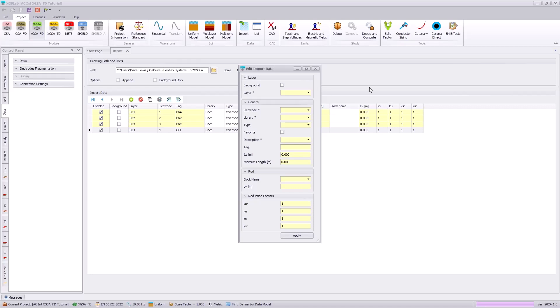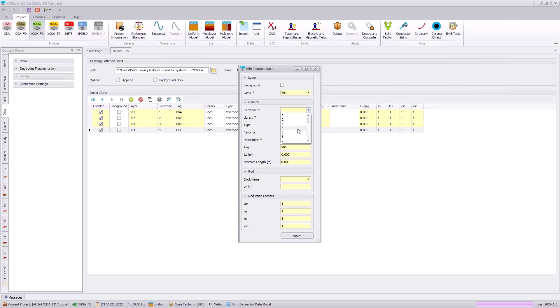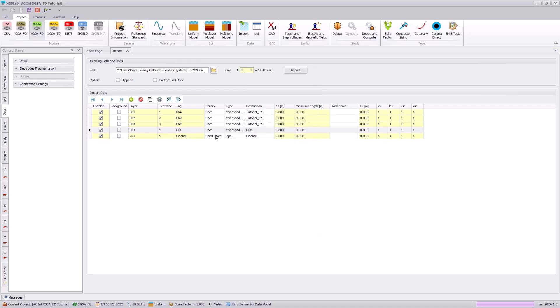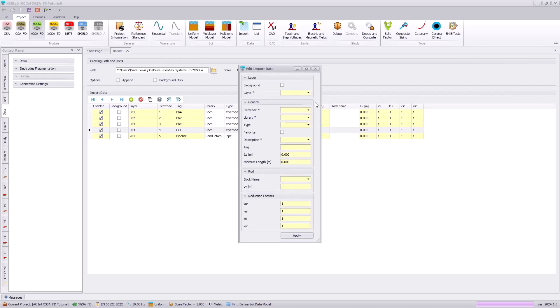We also need to import our pipeline that we will evaluate for induced voltages and currents. That will be coming from our V01 layer. We will specify this as electrode 5 and use a pipe type, specifying the pipeline conductor, and give it a pipeline tag name. Note we do not need to use any shifts in our Z axis because the CAD file we are importing from already has that information properly considered.